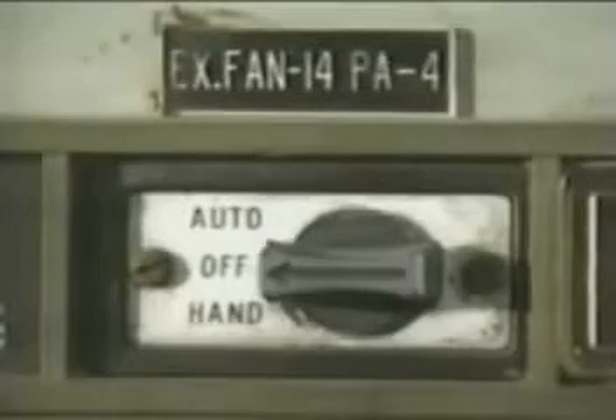If outside contractors perform service and maintenance at your facility, your employer and the outside employer will see to it that all workers understand and follow the proper procedures. When in doubt, check it out. For example, if you come across a closed valve or switch that has been turned off but doesn't have a lock, most likely someone has turned it off for a reason. Find out why it has been turned off before restoring power.